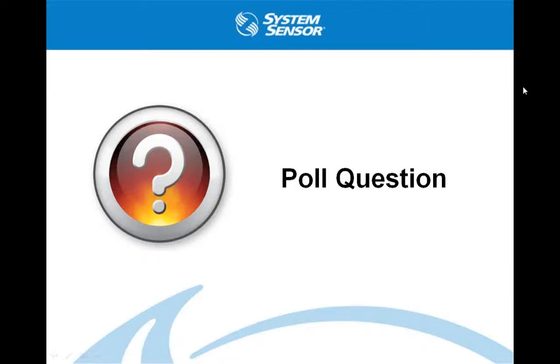One such area you might say is, okay, you're monitoring a return air grill in a certain facility or something like that. It would not be inconceivable that you could have 4 to 10 holes in a very short run of pipe within the ductwork, much like you would with a duct smoke detector. Again, because you're trying to identify just that very specific ideal location rather than trying to cover a vast area. Mm-hmm. Okay. So the PipeIQ software that does come with FAAST does a good job of helping you lay out those scenarios.